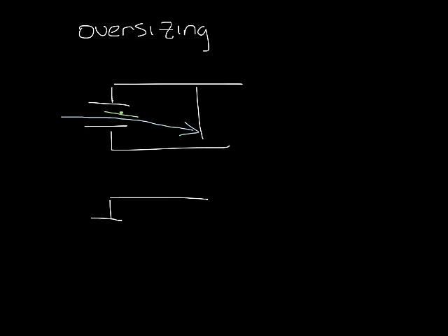Now let's draw a bigger box. In this case, the damper is going to be closed off more and it'll force the air towards the casing, and this can add sound to the box.